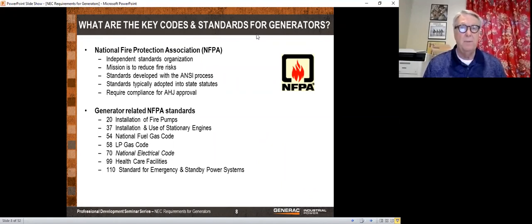20 is on fire pumps, 37 is on engines, 54 is the fuel gas code, 58 is LP, which is liquefied petroleum. 70, of course, is the National Electrical Code. That's standard 70. Then 99 is healthcare, and 110 is the big one, standard for emergency and standby power systems. All of those really have some bearing upon the proper design and installation of a generator. And so we will get into those next week.